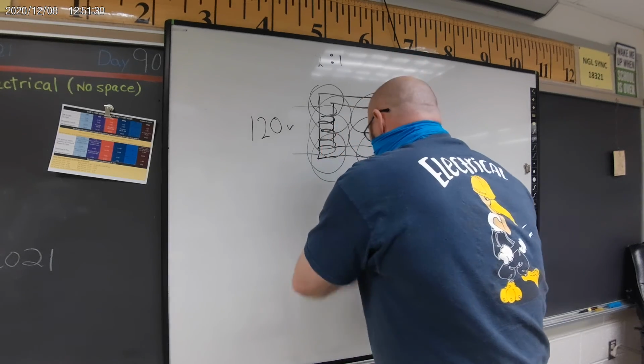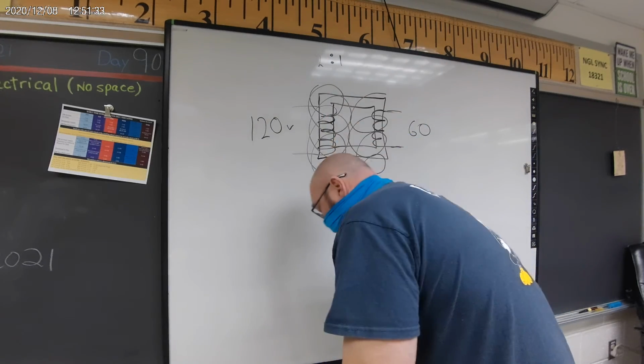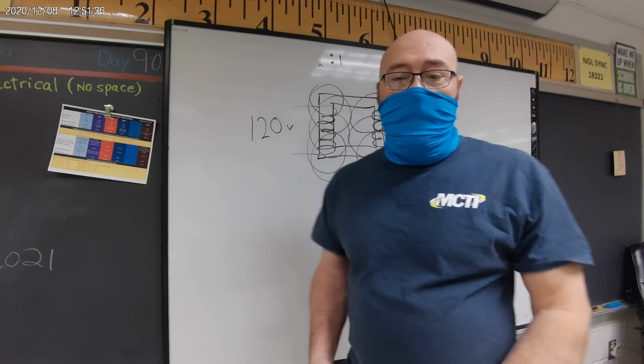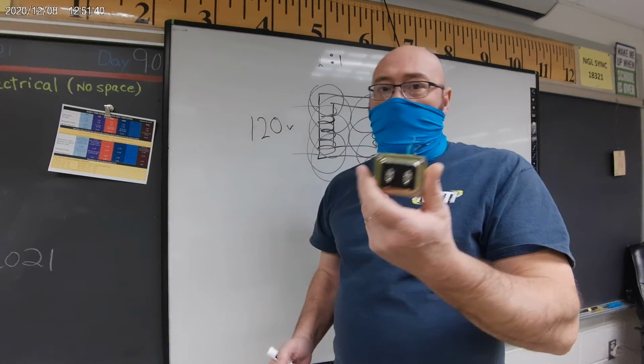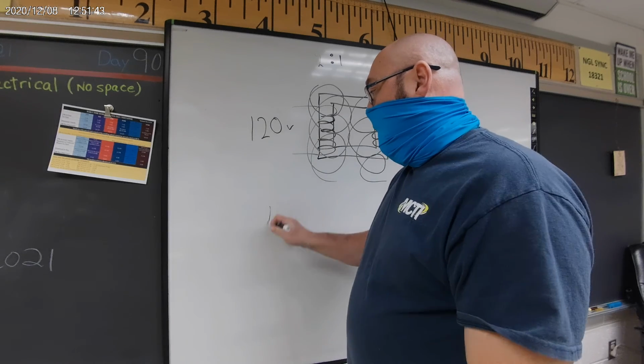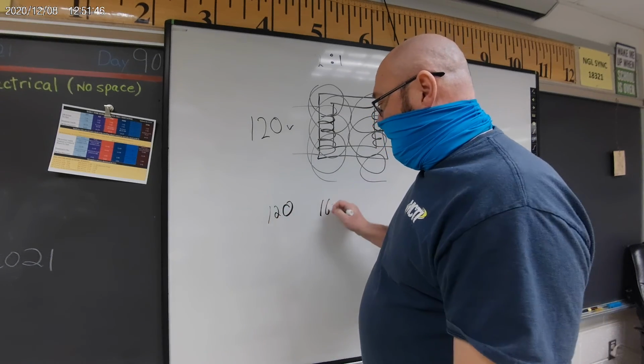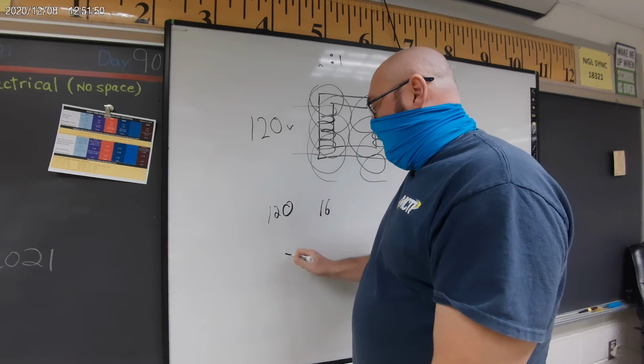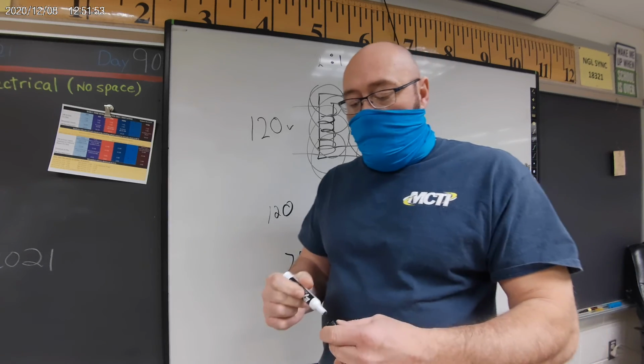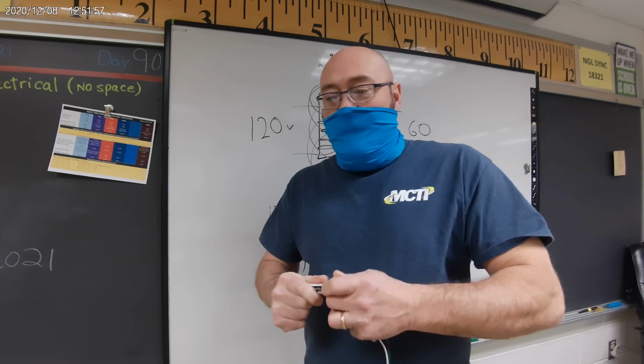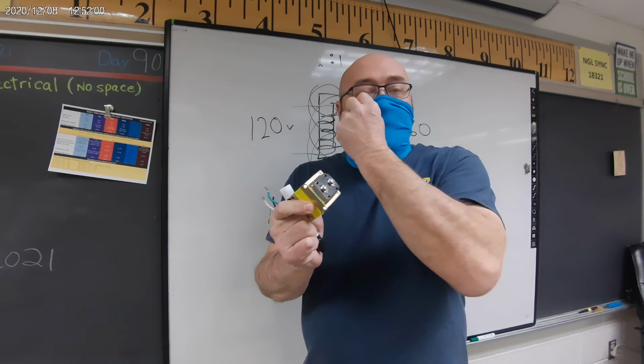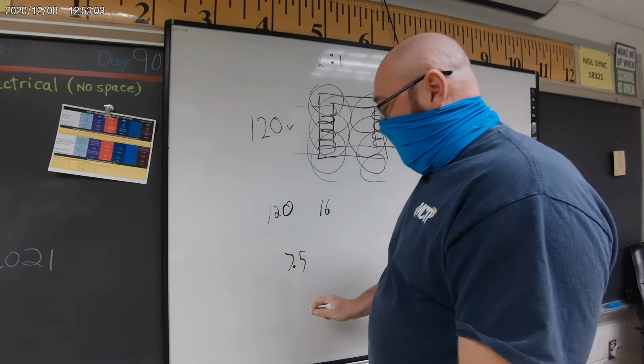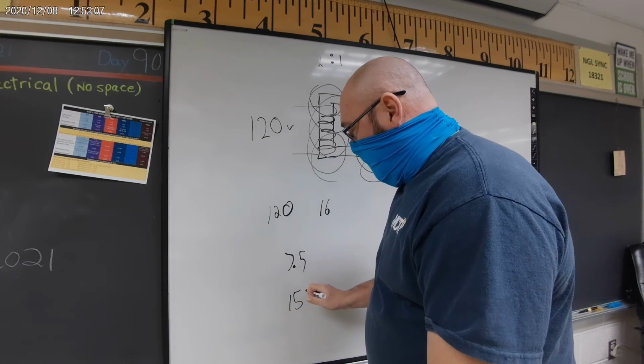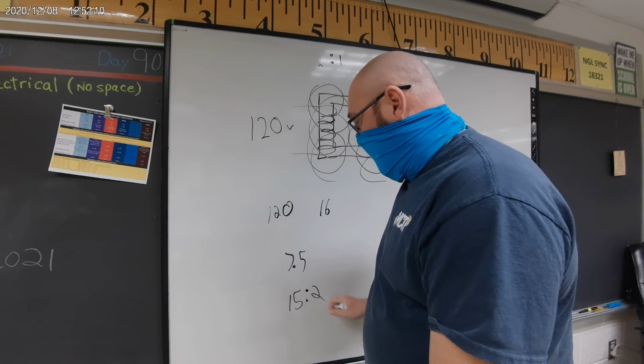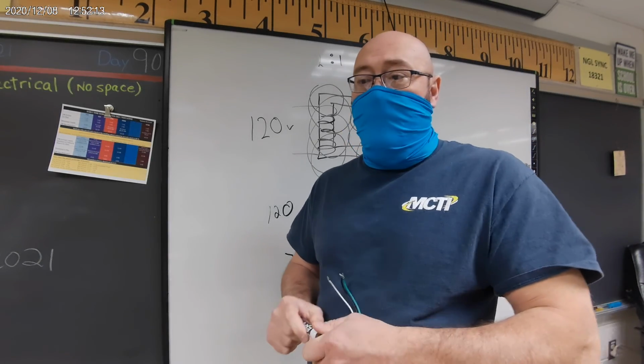So I want to show you something here. Don't always think that it is a 2 to 1, a 30 to 1, or a 60 to 1, because with this transformer, I put 120 volts into one side, and I'm only getting 16 out of the other. So if I just divided that, it's going to come out to 7.5. Well, how could I have a 7.5 to 1? I can't have half a winding. But if I doubled it, for every 15 windings on my primary side, I have 2 windings on my secondary side.